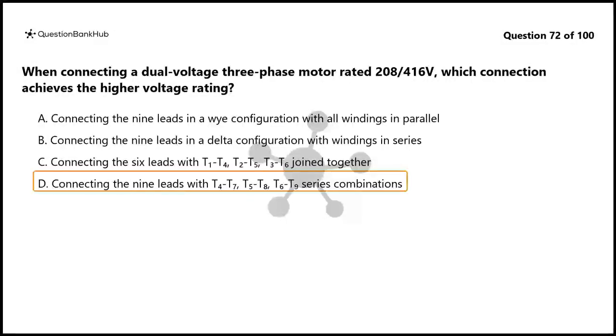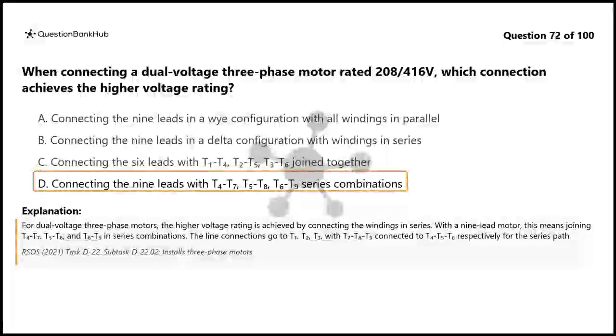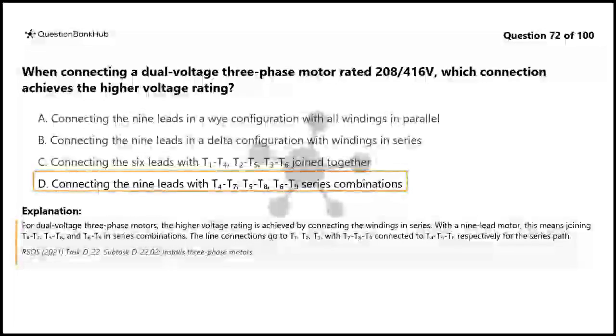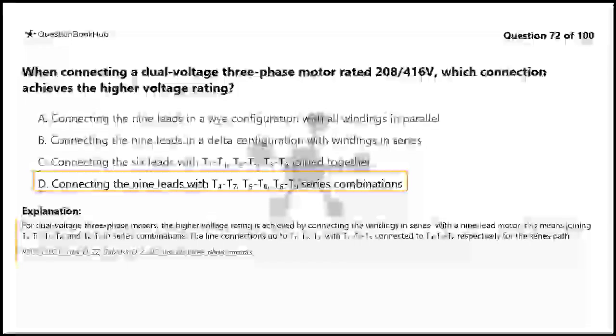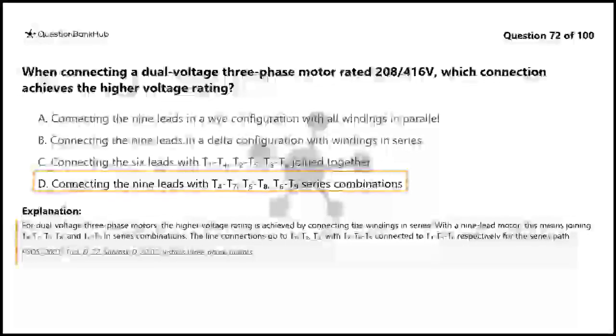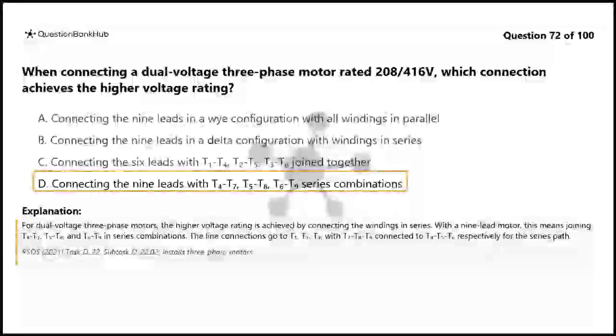The correct answer is D. Connecting the 9 leads with T4, T7, T5, T8, T6, T9 series combinations. For dual-voltage 3-phase motors, the higher voltage rating is achieved by connecting the windings in series. With a 9-lead motor, this means joining T4, T7, T5, T8, and T6, T9 in series combinations. The line connections go to T1, T2, T3, with T7, T8, T9 connected to T4, T5, T6 respectively for the series path.